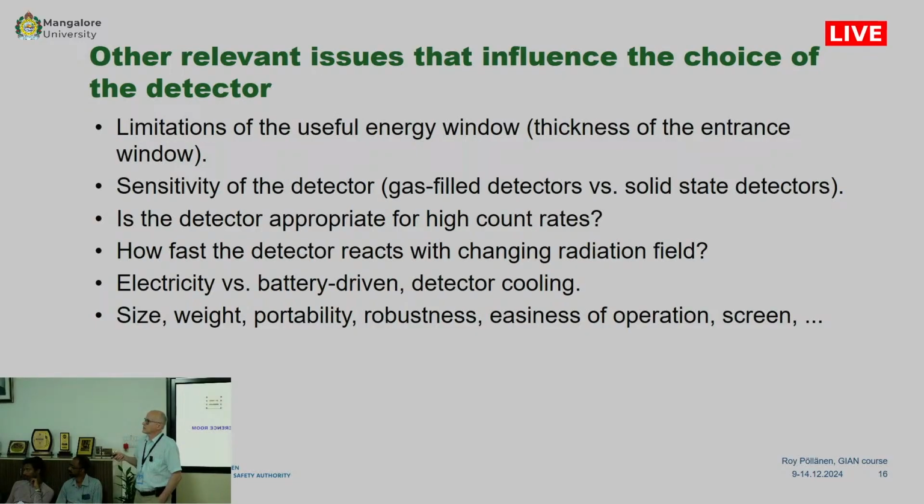One thing regarding the choice of the detector is this: is it battery driven, or how is the detector cooled? These are very important when you have to do measurements in the field.